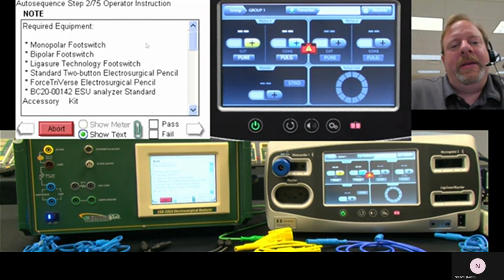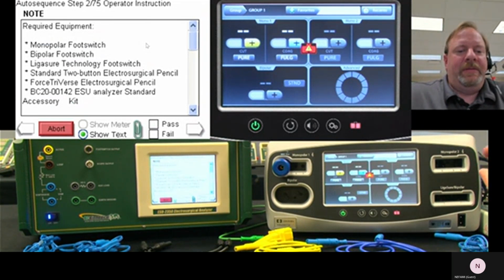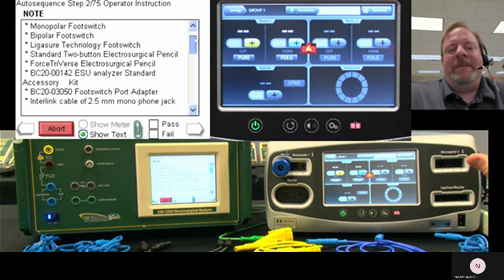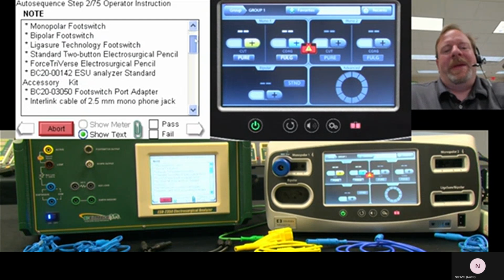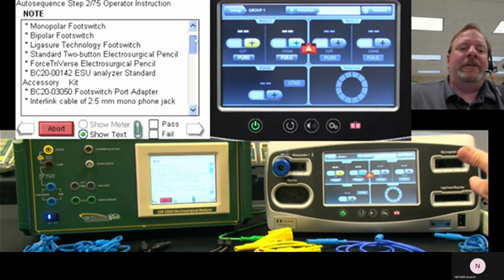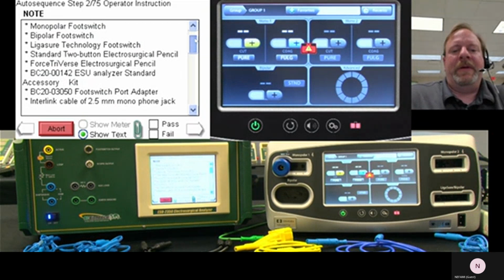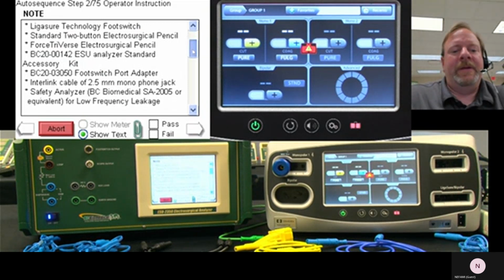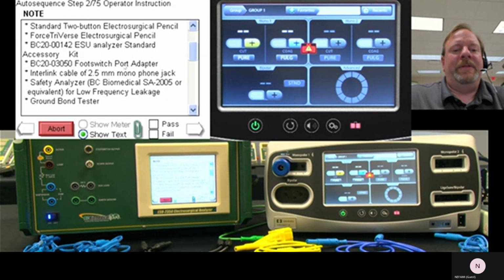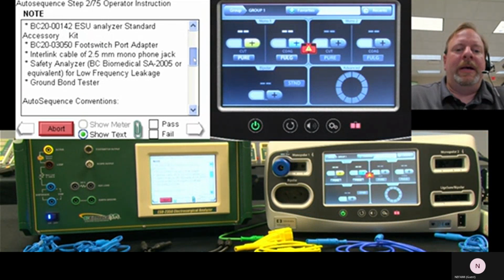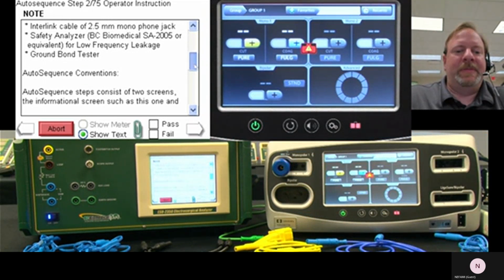First we have to do, as we read the instructions, the required equipment. We have to make sure we have everything we need. So this is based on the service manual. This is what Covidien tells you you need in order to test the generator. You need all the pencils, you need the foot switch, you need all this other stuff. In this case, we added the foot switch port adapter. You do need that for this testing. And then everything else is specified by the service manual.